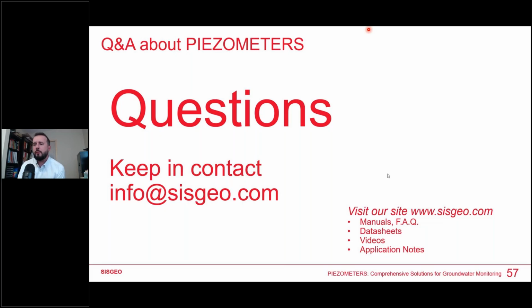What is the range of permeabilities of ground where a piezometer sensor in vibrating wire mode can be used? I would say any, because we have different ways to equip the filter, so filter in HAE or filter in LAE. But basically, if you read carefully again the presentation, then you should not use a piezometer when the particles are thinner than 1 micrometer. I don't know if it's common. I think in clays somehow you can maybe have this effect, and this dimension. But range of permeabilities are, I would say, all.